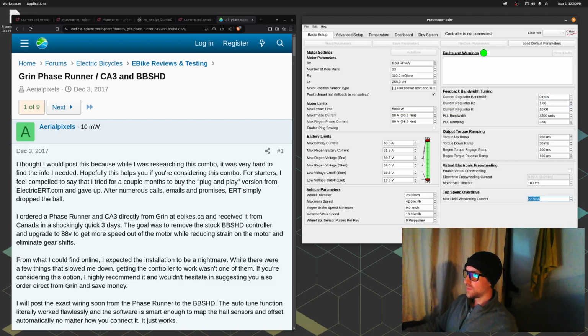But then after that, my experience has been that you have to change this PLL bandwidth and the PLL damping. It says the PLL bandwidth is a feedback term for the controller's phase lock loop that tracks the rotational position of the motor. This term can have a significant effect on controller motor oscillations and vibration at various speeds.